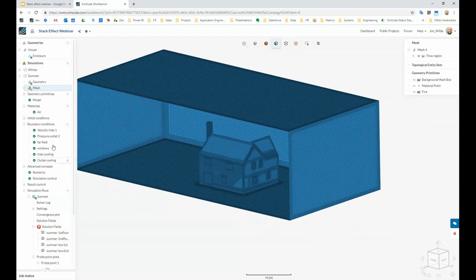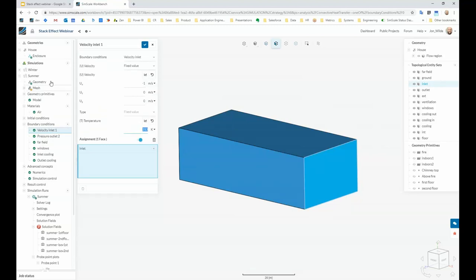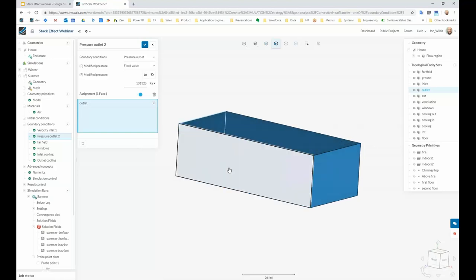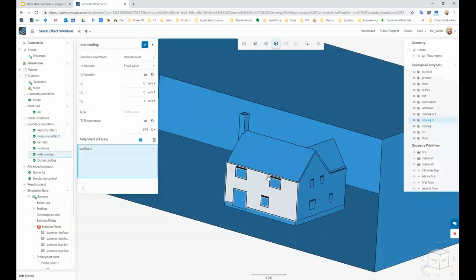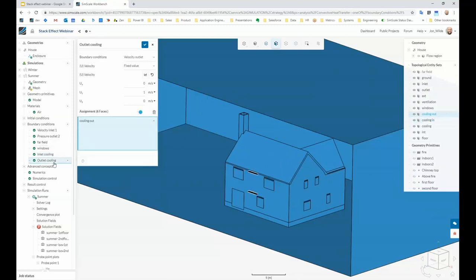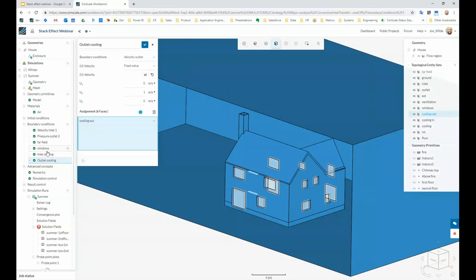Once at this point, we need to start telling SimScale what we know. On the right-hand side we have a velocity inlet — one meter per second with an inlet temperature. This is our summer condition so it's a little warm. On the other side we have our outlet where flow will exit. For the summer scenario we have inlet cooling — inside on the air conditioning units, air exits at a cooler temperature. We also have air being pulled into those units at a specific flow rate. That pretty much covers the setup: import your geometry, automatically mesh it, and then the detail part is telling SimScale everything you know to get correct results.